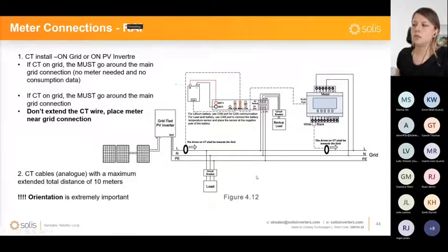So that was a good thing, but because this design did not allow any information regarding what the PV inverter was actually generating, there were no consumption values available on the inverter itself. Also, the cable for the CT clamp could not be extended. So the RAI was always installed in a more remote place because it needed to be right on the grid connection point, and it was causing a little bit of trouble. That's why we have now launched the version with the meter integrated.